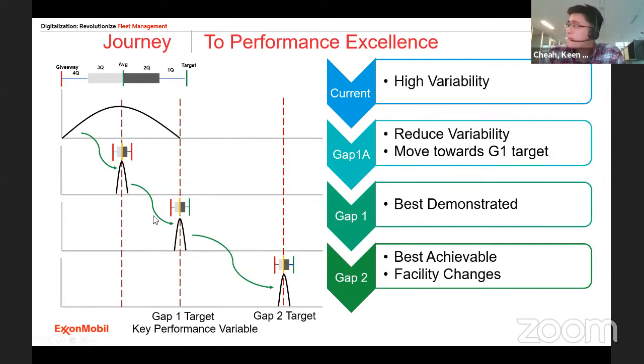Gap 1 is really moving towards a historical best demonstrated performance. It's the economic penalty that exists due to the difference between current operating conditions and the best demonstrated values. Examples of this could be exchanger fouling or heater fouling, things that have prevented us from achieving the energy efficiencies we want. Such differences can typically be closed via engineering and maintenance excellence.